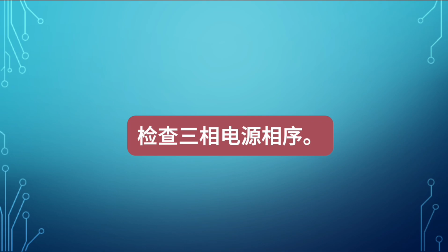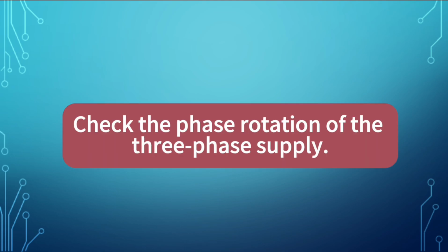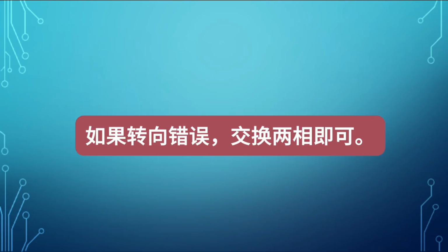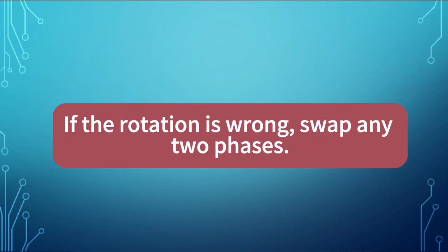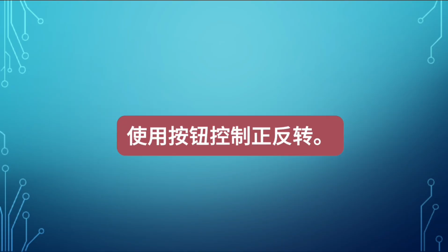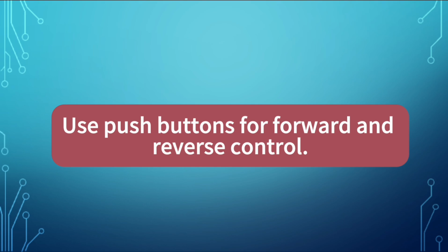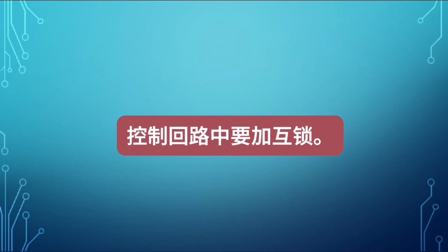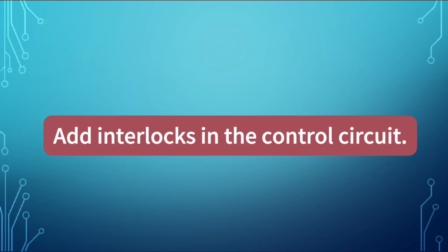Check the phase rotation of the three-phase supply. If the rotation is wrong, swap any two phases. Use push buttons for forward and reverse control. Add interlocks in the control circuit.